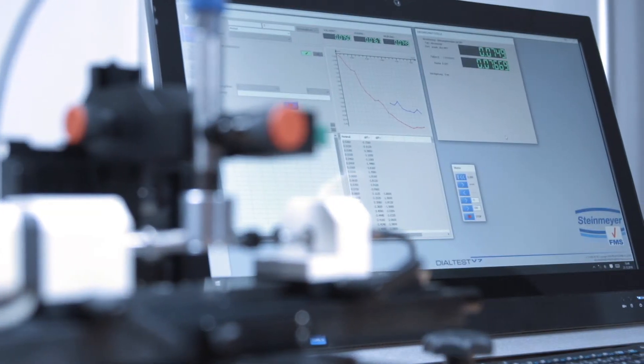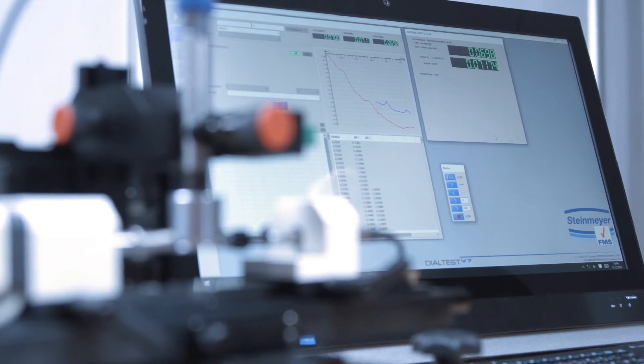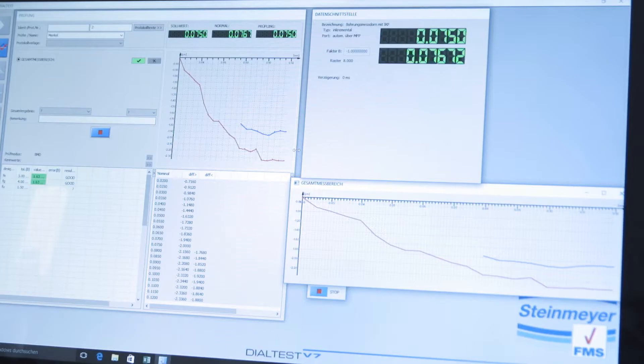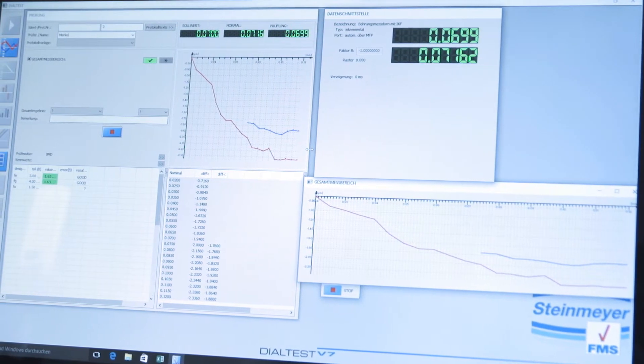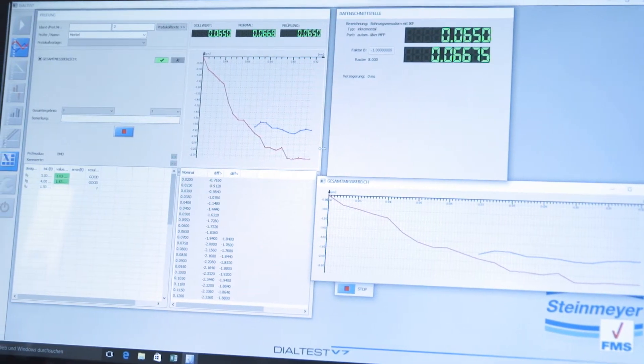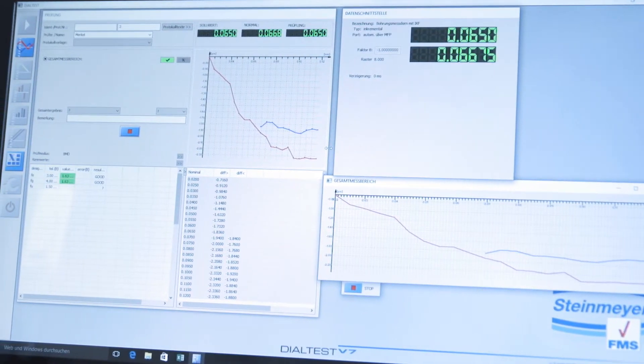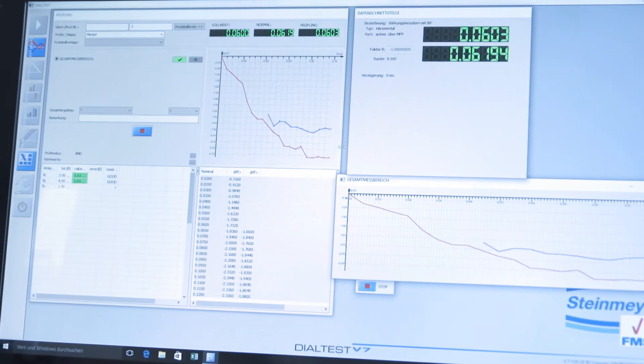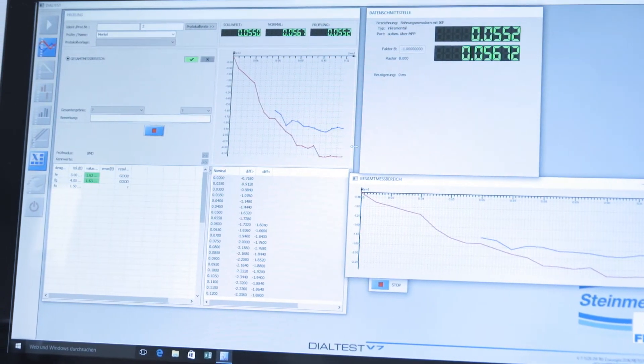The test steps saved in the testing software DIALTEST are executed completely automatically, and that for both incoming and outgoing test directions. This is the only way to find damage to the mechanics or possible reversal ranges.